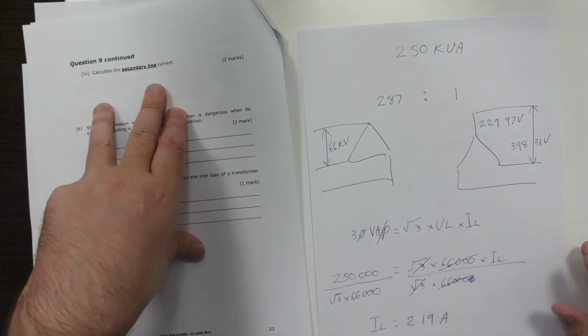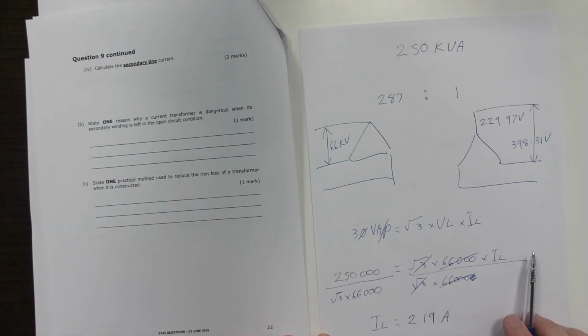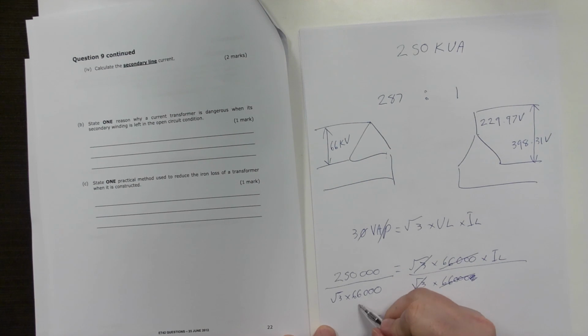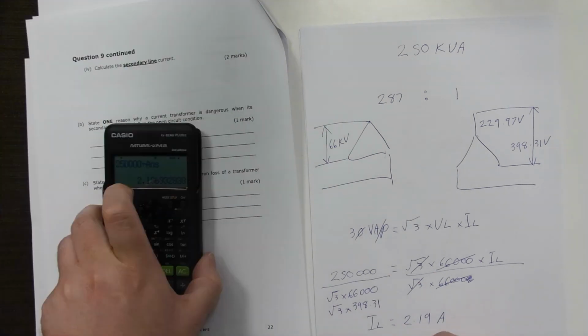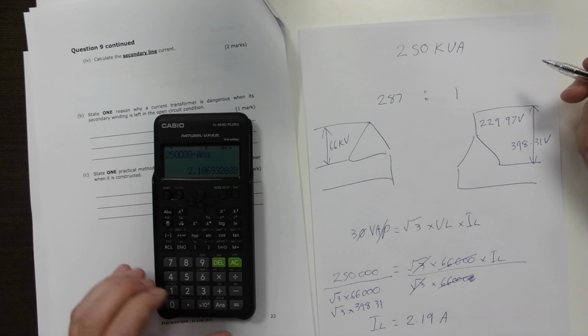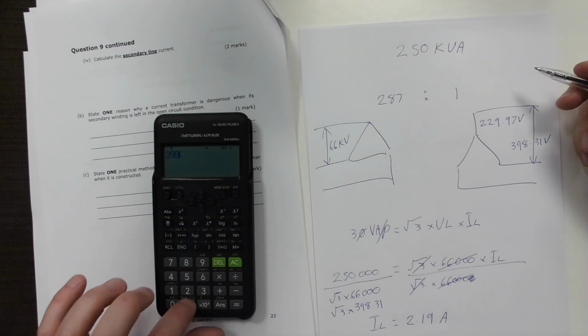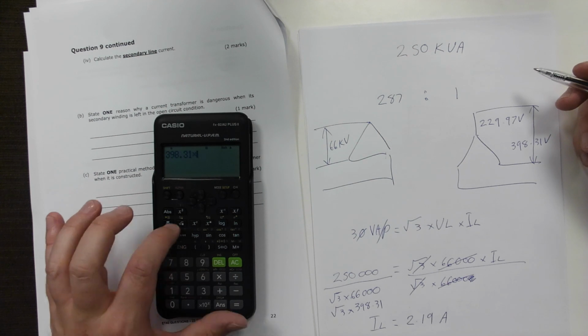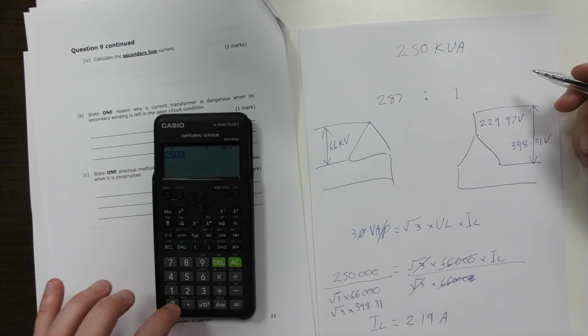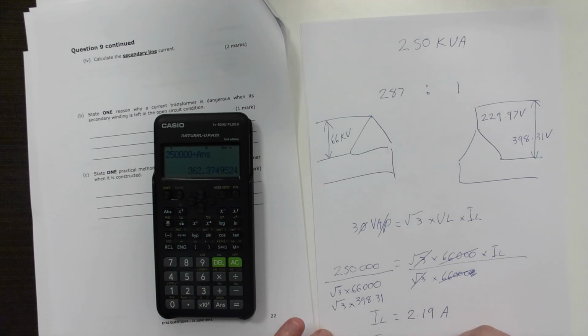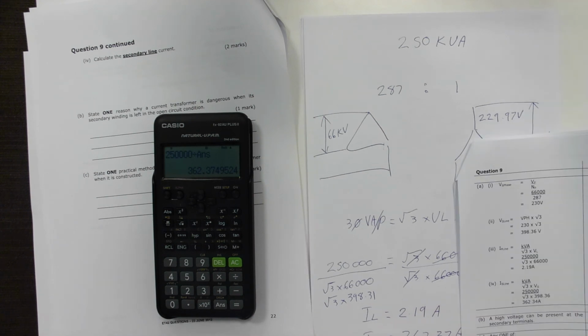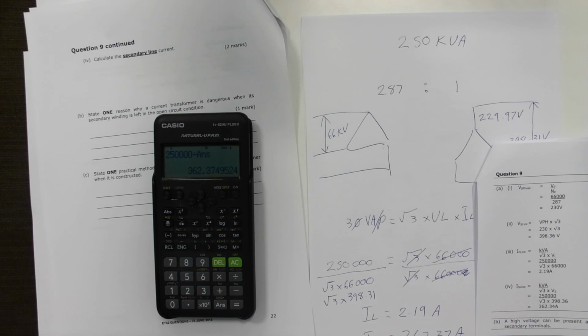Now calculate the secondary line current. So the formula doesn't actually change. However, our line voltage changes. So instead of 66,000, we're using 398.31. So that's still square root of 3 times, and that's still 250,000. And so our I line equals 398.31 times square root 3 equals, and then our 250,000 divided by answer gives us 362.374, so 362.37 amps. We look at our answer sheet once again, they had 362.34. That's a rounding error difference. Once again, it will be ignored.